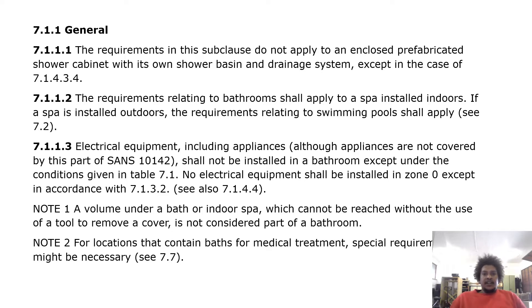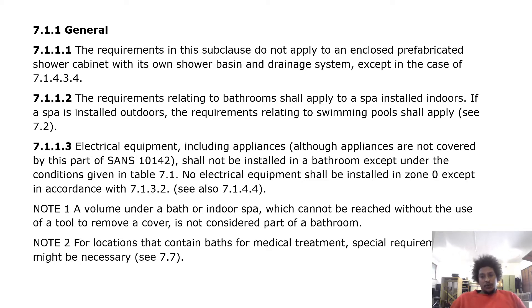General: the general requirements in this sub-clause do not apply to an enclosed prefabricated shower cabinet with its own shower basin and drainage system, except in the case of 7.1.3.4. The requirements relating to bathrooms shall apply to a spa installed indoors. If the spa is installed outdoors, the requirements relating to swimming pools shall apply.